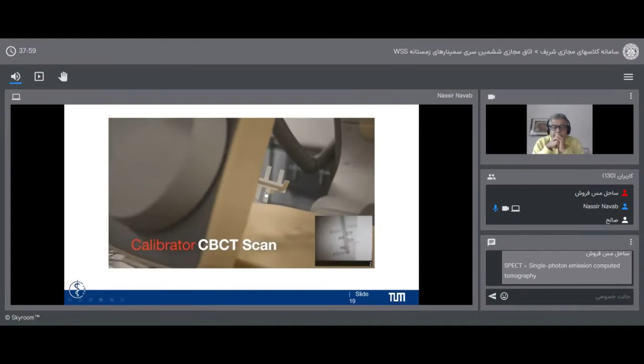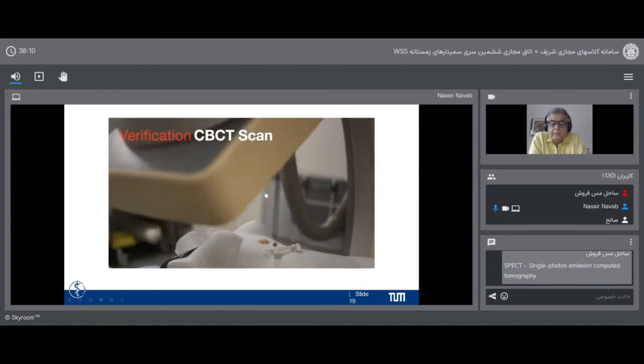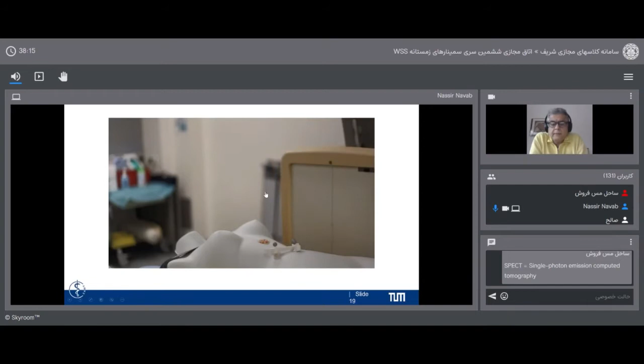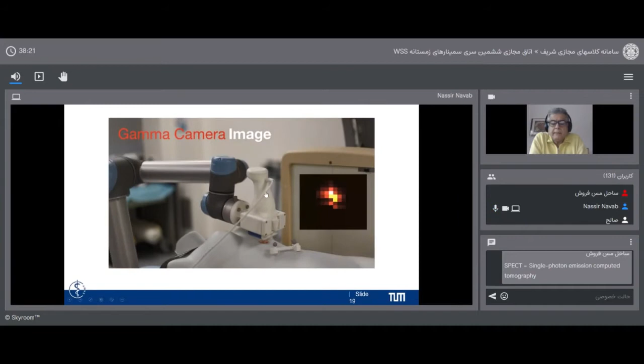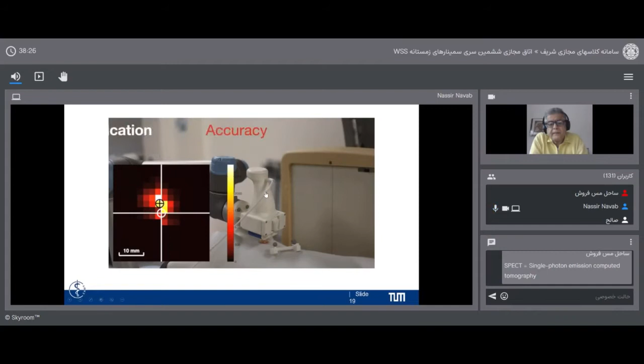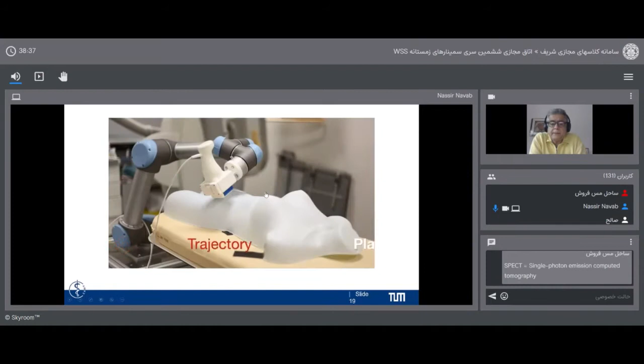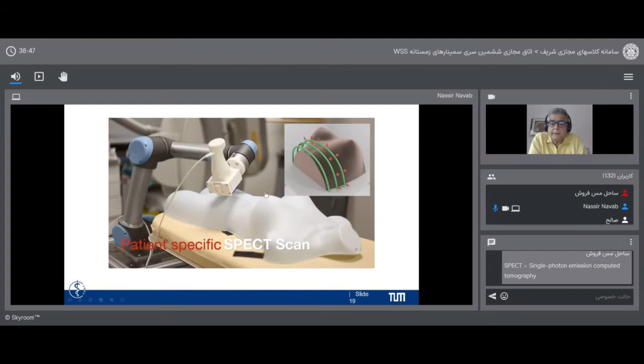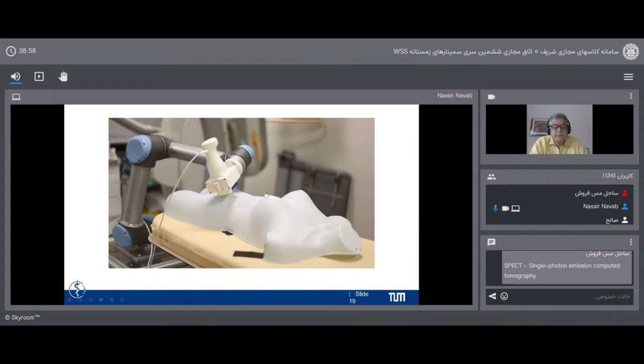And then in 2014, for the first time, we were able to do intraoperative SPECT CT by doing a cone beam CT acquisition, then having the two robots, the X-ray robot and the gamma robot, what we call kissing each other, to make sure that they are in the same coordinate system, to co-calibrate themselves and make sure that the accuracy is on the order of sub-millimeters or a millimeter. Based on the cone beam CT acquisition, the doctor would say, this is my area of interest. And then the robot would compute a trajectory to optimize the estimation of the radioactive measurements in that area, and then do a SPECT reconstruction. That would mean in less than about 5 minutes, we would have intraoperative functional and anatomical images ready for use by the surgeon.